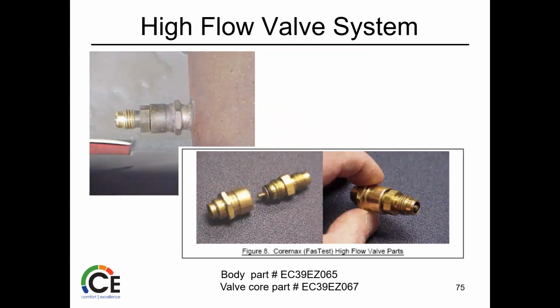This one throws guys off a bit. A high flow valve system. It's only used by the factory. Takes a special tool to take it apart. You can replace it. If it leaks, they do tend to leak over time, just like everything else. Part number is there. It's called CoreMax, or a high flow valve. Again, it's only the factory. So if you want to grab one and replace it, great. If you want to try and seal it off somehow, that's great too. Nobody's ever going to say anything to you.